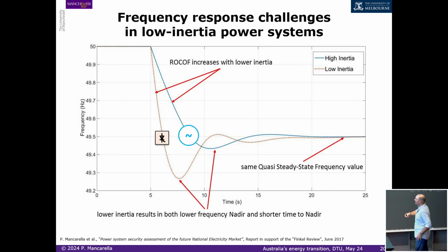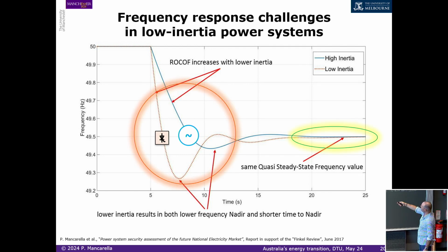So effectively you have a typical case where regardless of how much capacity and potential steady-state reserves you have in the grid, dynamically your frequency response when you lose a generator, an interconnector, or whatever, really depends on the level of inertia.